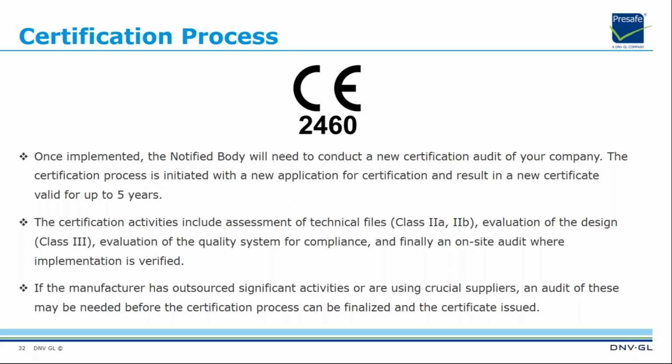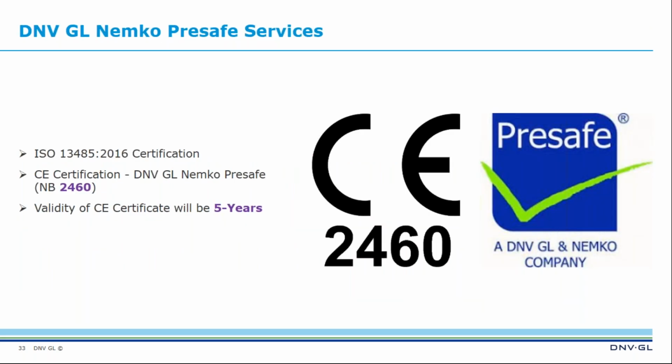The certification activities include assessment of technical file for Class 2A and Class 2B, evaluation of the design for Class 3, evaluation of the quality system for compliance, and finally, an on-site audit where implementation is verified. If the manufacturer has outsourced significant activities or is using crucial suppliers, an audit of these may be needed before the certification process can be finalized and the certificate issued.